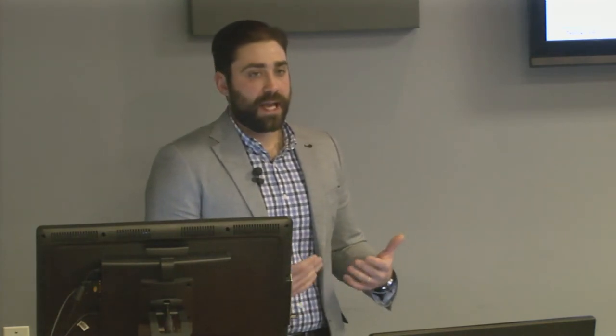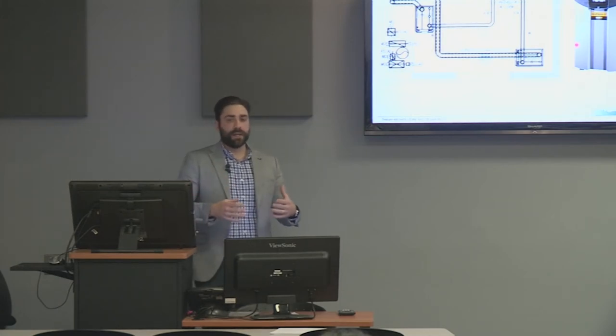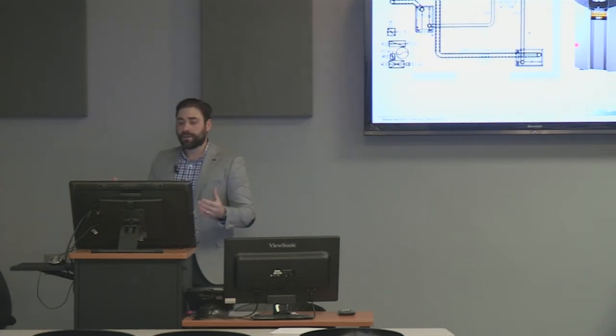We're using gas-fired condensing boilers — two Laars Neotherm condensing boilers that are 96% thermally efficient. We're producing domestic hot water that goes into 500-gallon, well-insulated storage tanks, so hot water is available on demand. The piping runs are very short, minimizing the distance between the hot water heaters and the storage tanks. Having these on the roof also adds to resiliency by keeping vulnerable mechanicals out of harm's way.